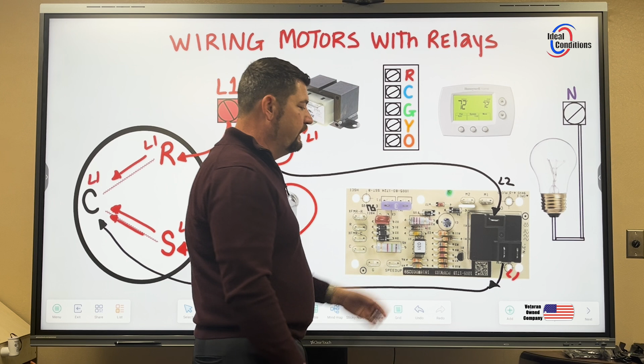So what we're doing is, if I'm L1 here and through the winding, then I'm L1 here and the same here, right? And so that means back here I'm also reading L1. So if that relay is open, I'm actually reading 2 legs of power. So those 3 values that I told you I would go over, I'm starting to go over them now. We're going to read the value of L2 plus L1, which is 2 different legs. And those 2 different legs read 2 different voltages. 120 plus 120 is 240. So I'm going to read 240 across these 2 points with my meter. And I'm going to leave that there until those values change.